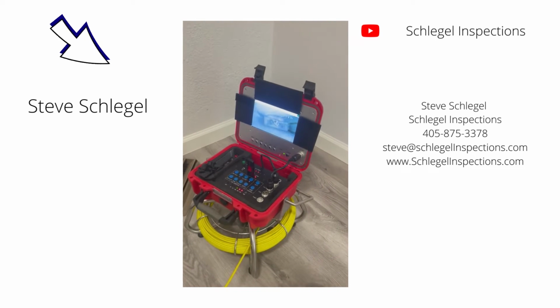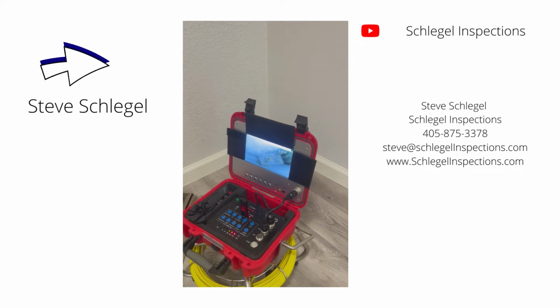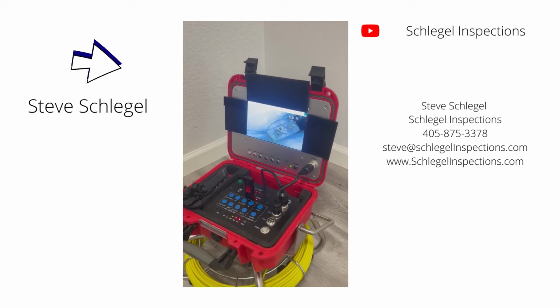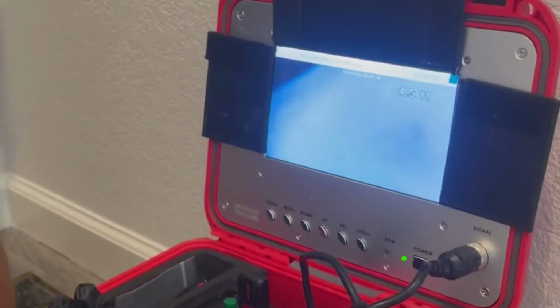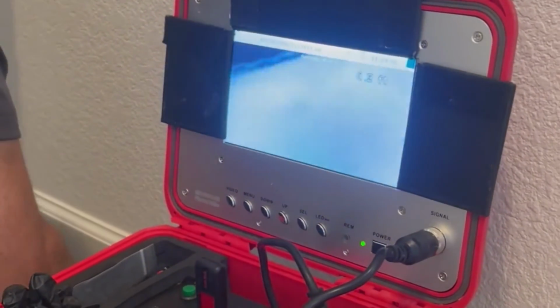Not a lot of debris, and that's good, because there would be an accumulation of sand or what have you, and or other corrosion in this area, especially if there was a lot of moisture. So this looks actually really clean for the age of this house. Minor corrosion in the register, but I'd say that's commensurate with age, so it's not really any significant.